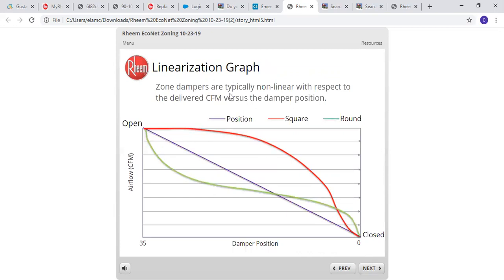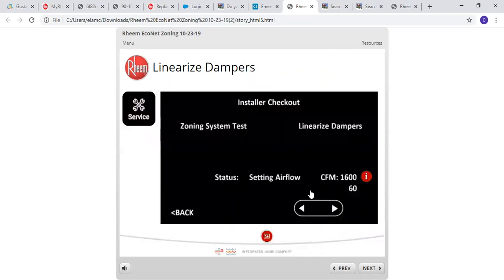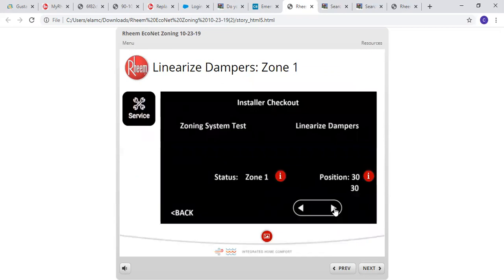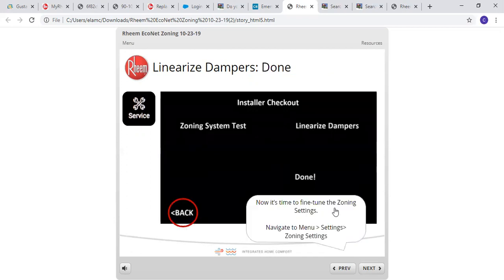Linearization graph. So your zone dampers are typically non-linear with respect to the delivered CFM versus the damper position. So whether it's a square, round position. Okay, so we're going to do a checkout here. Zone 1, Zone 2, Zone 6. Now it's time to fine tune the zoning settings.